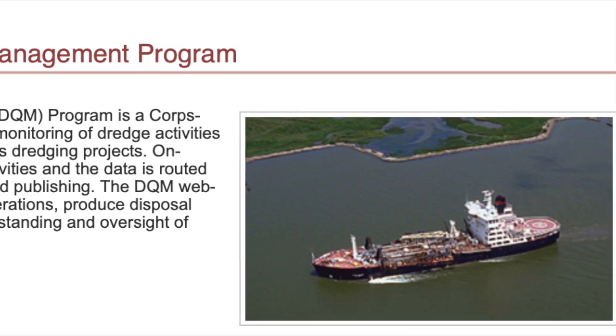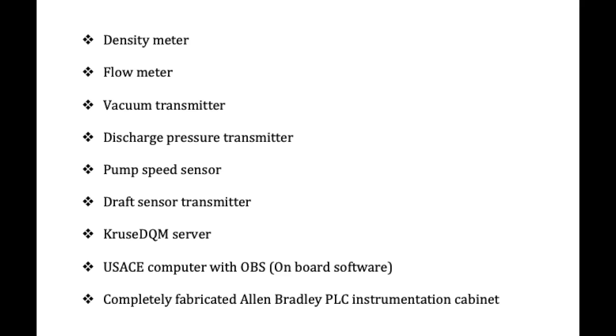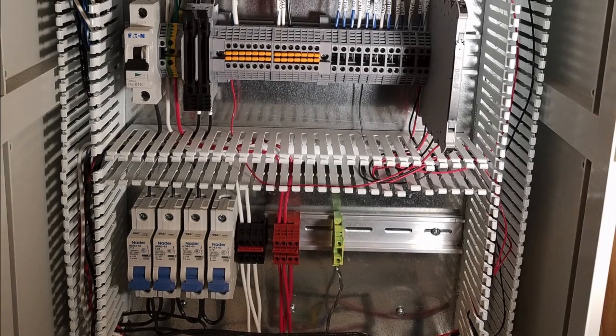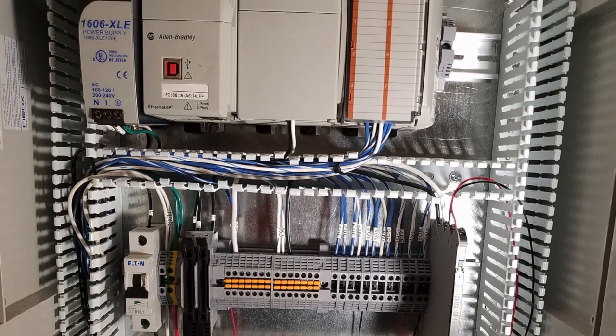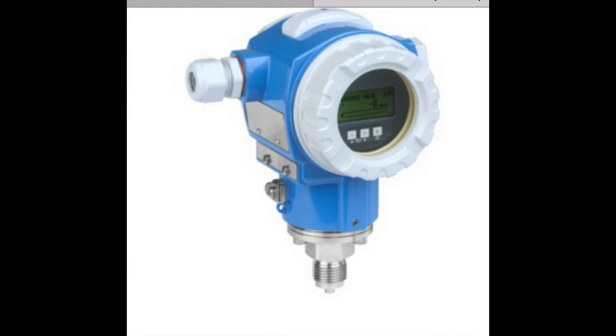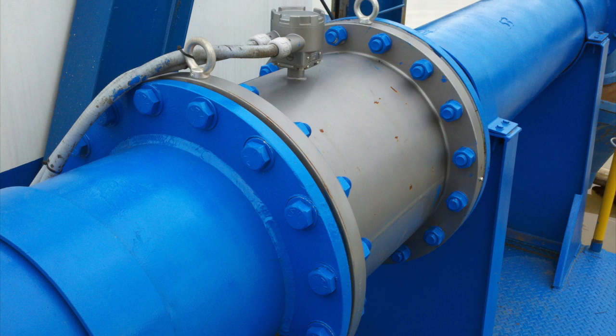KruseDQM includes all of the instrumentation, computers, and software necessary to comply with the spec. Specifically, the density meter, flow meter, vacuum transmitter, discharge pressure transmitter, pump speed sensor, draft sensor transmitter, the server holding the KruseDQM software, and a computer for the Army Corps OBS onboard software, as well as the completely fabricated Allen Bradley PLC instrument cabinet. Note that any of the instrumentation mentioned that already exists on your dredge could be used for this DQM package.